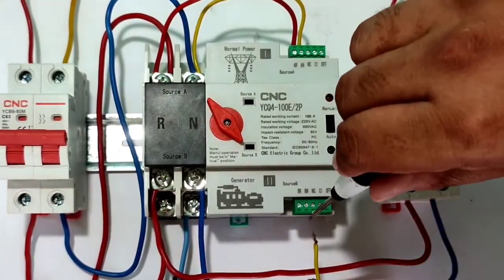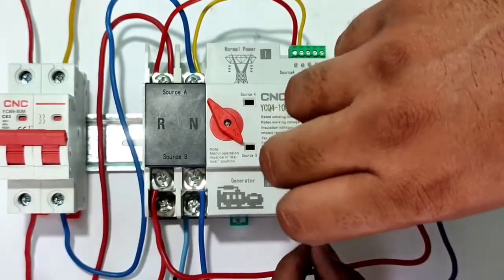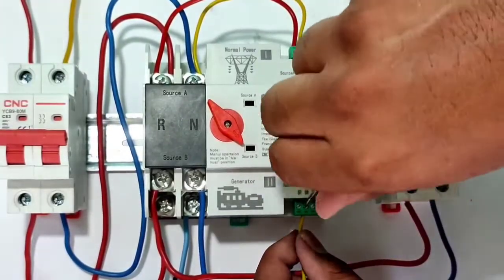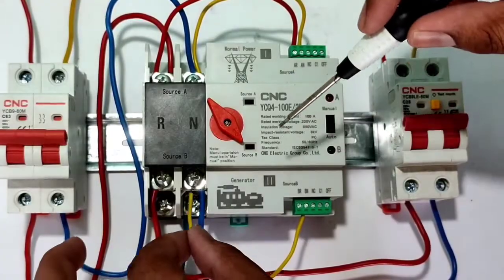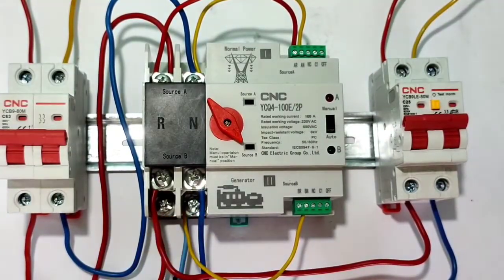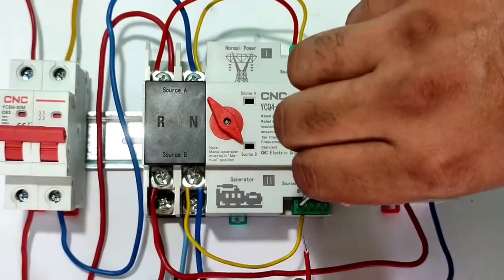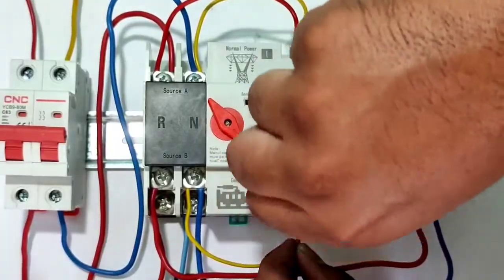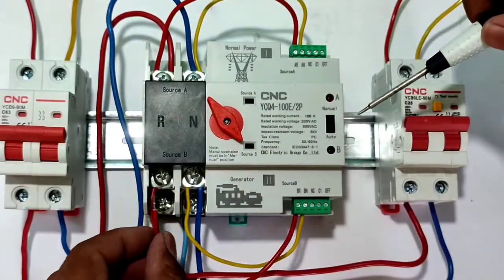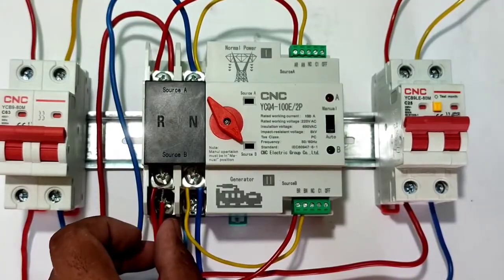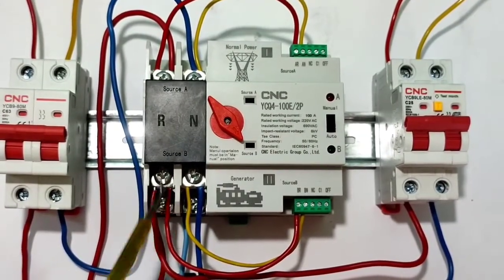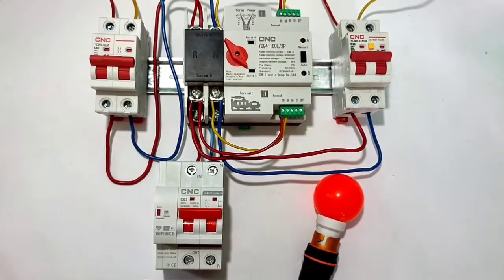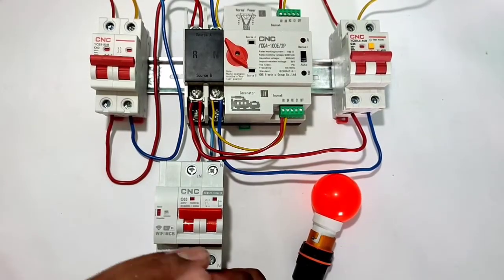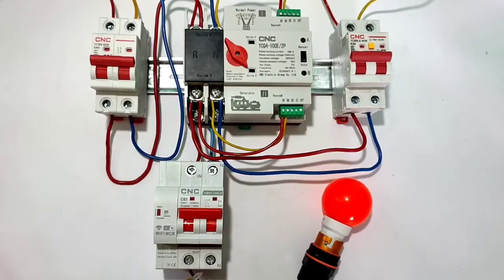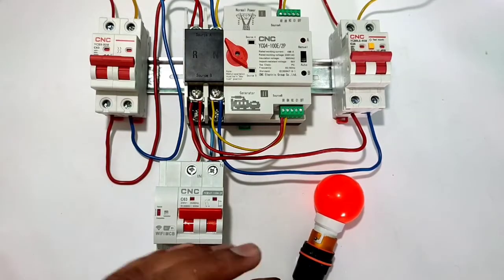Okay, now the same connection for source B. We connect one connector from the BN terminal for the neutral wire, BN terminal to the source B N terminal. Now connect a phase wire from the B R terminal to the source B R terminal. Okay, it's a very simple control wiring. Okay, now our power and control wiring is done. Now connect the load MCB output wire, to which we connect one load. So we connect a phase wire to the output MCB here and the neutral wire here.